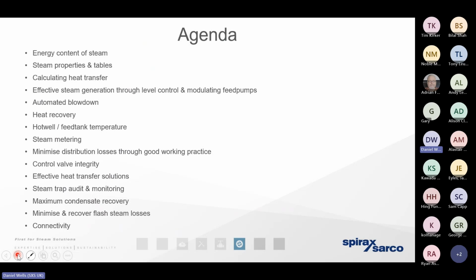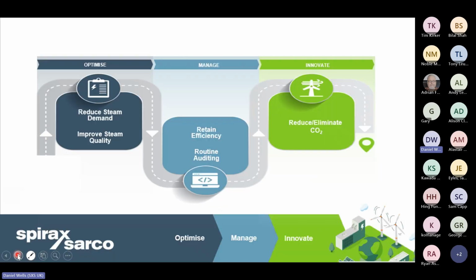One of the first things that we need to remember is whenever we're engaging with our client's steam system, that steam system could have been engineered 20, 30, or even more years ago. So it could have been engineered at a time when the cost of gas, the cost of water, the cost of steam was relatively cheap, where we'd never heard of carbon emissions, and where we lived with the inefficiencies that may exist within the steam system. Sure, we might be aware of different areas where we can optimize and improve that efficiency, but the payback may not have been too attractive at that time. So we lived with that inefficiency. But fast forward 25, 30 years, and the cost of steam, the cost of gas, and those carbon emissions are creeping up on us over time. They're unwanted. So we're really going to look in some detail with regards to where those inefficiencies may exist.